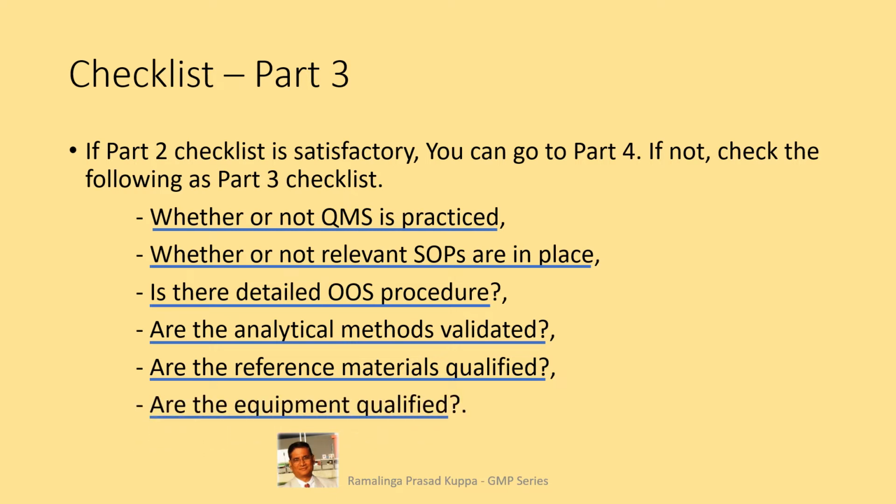Are the equipment qualified? Equipment qualifications, requalifications, preventive maintenance, etc. should be checked in detail. Entire history records of the equipment should be verified for establishing its working condition.